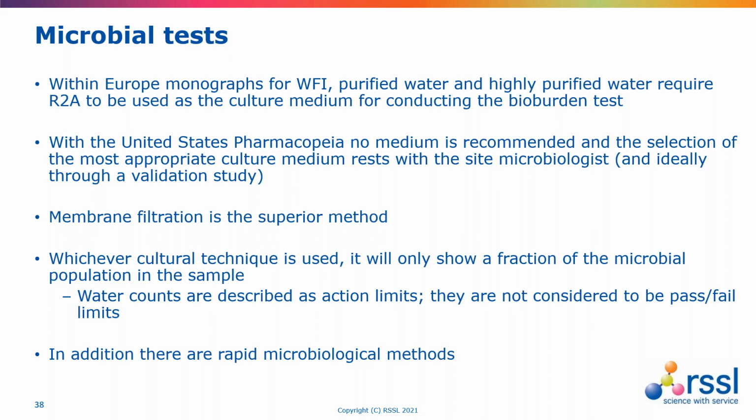And there's a choice of method, so purified water can be tested by pour plate or membrane filtration. Membrane filtration is the superior method, and membrane filtration is required for WFI. Obviously, if we're diluting water, we need to make sure we're still able to produce a population count that's within the limit of the water itself.